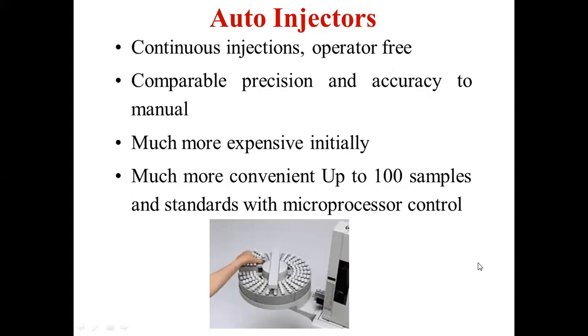Once the sample is aspirated, sodium, calcium, potassium, lithium, and strontium, all these elements can be detected at a time by means of that microprocessor. So like this, if you have introduced 100 samples in these injectors, it is very easy for the microprocessor to select the samples at different time intervals.